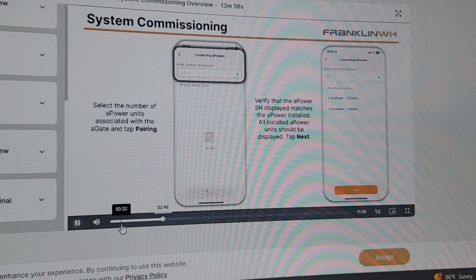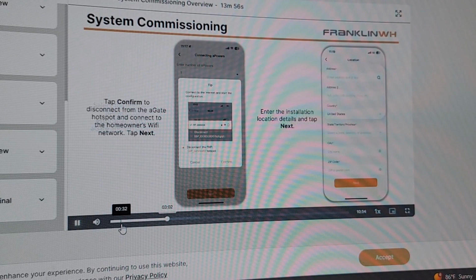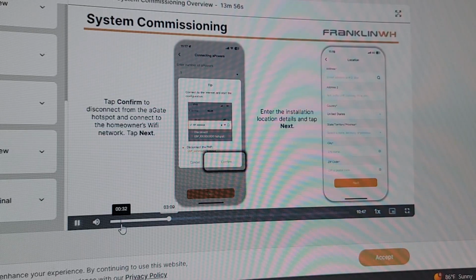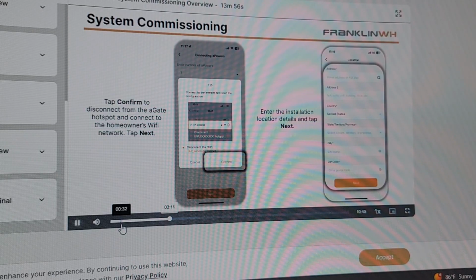Select the number of aPower units associated with the aGate and tap Pairing. Verify that the aPower serial number displayed matches the aPower installed. All installed aPower units should be displayed. Tap Next to continue. Tap Confirm to disconnect from the aGate hotspot and connect to the homeowner's Wi-Fi network. Then tap Next. Enter the installation location details and tap Next.